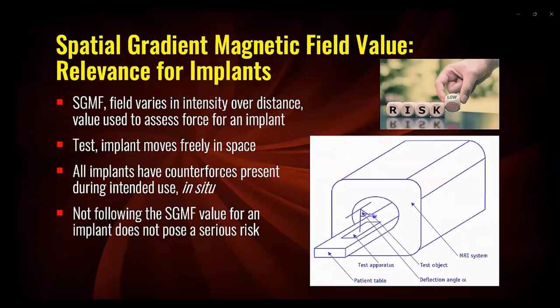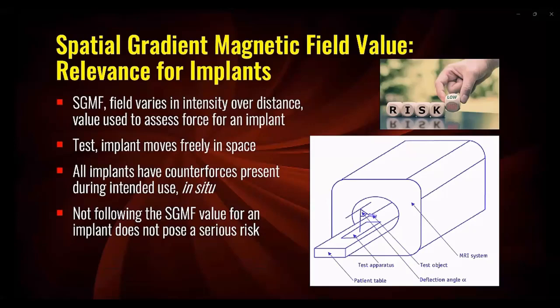When such testing is performed, the implant is suspended by a string and therefore freely able to move in space. The resulting information is the value of the spatial gradient magnetic field used for the force test, and that information becomes part of the MRI labeling for the implant.